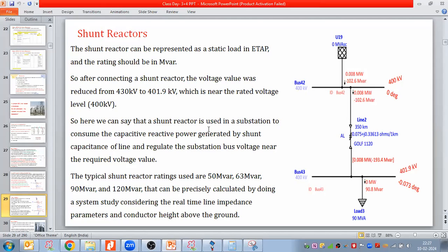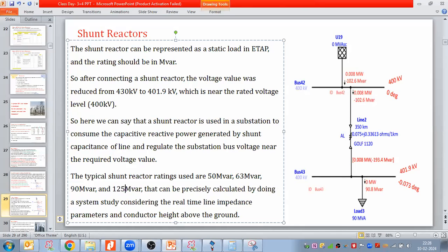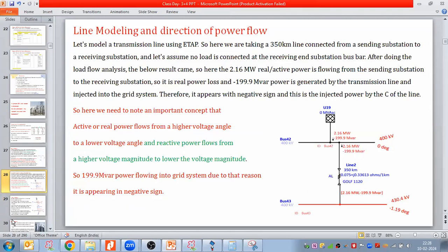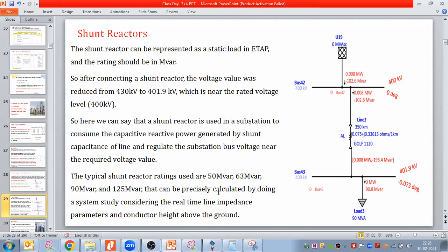So here we can say that the shunt reactor is used in substations to consume the capacitive reactive power generated by the shunt capacitance of the line and regulate the bus voltage near to the required rated voltage. The typical shunt reactor ratings are 50 MVAR, 63 MVAR, 90 MVAR, 120 or 125 MVAR, and that can be calculated precisely by doing a system study considering the real-time line impedance, the real-time line length, the real-time line conductor height above the ground, and precisely we can calculate what should be my rating of the reactive power.